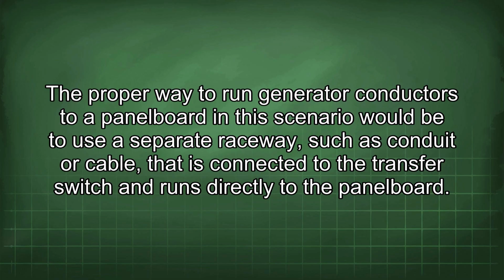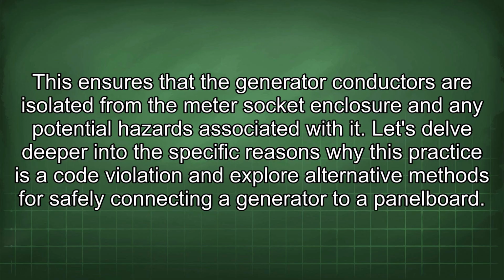The proper way to run generator conductors through a panel board in this scenario would be to use a separate raceway such as conduit or cable that is connected to the transfer switch and runs directly to the panel board. This ensures that the generator conductors are isolated from the meter socket enclosure and any potential hazards associated with it.